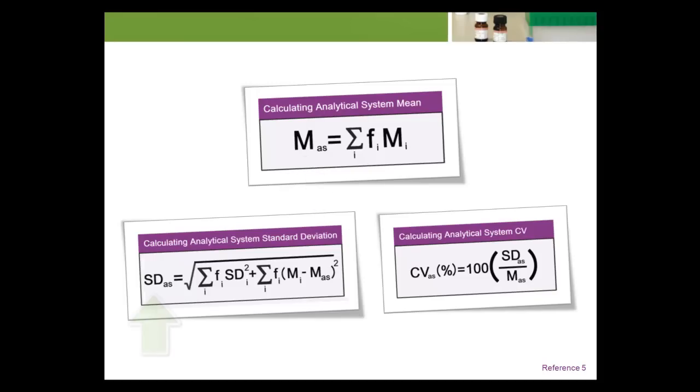MAS, SDAS, and CVAS are the mean, standard deviation, and coefficient of variation for the total analytical system. In these formulas, FI represents the fraction of patient samples tested on the Ith analytical module of the system. MI is the mean level, and SDI is the standard deviation for the Ith module based on repeated testing of a specimen. MI and SDI can be based on quality control data and easily obtained from QC management software.